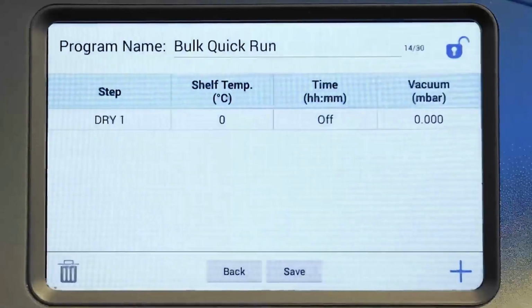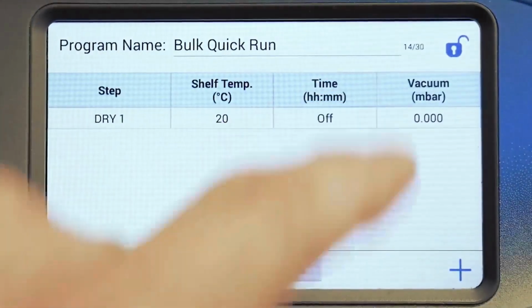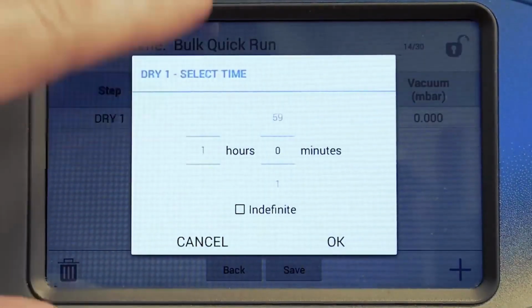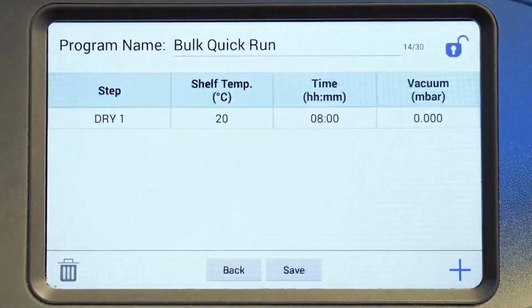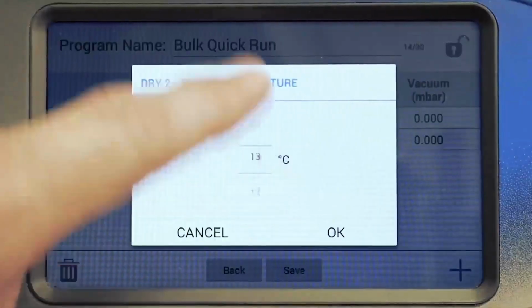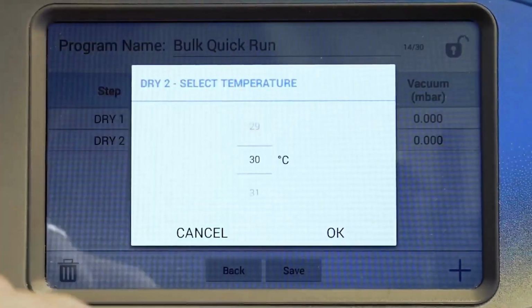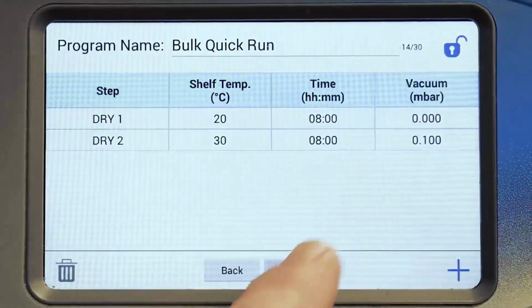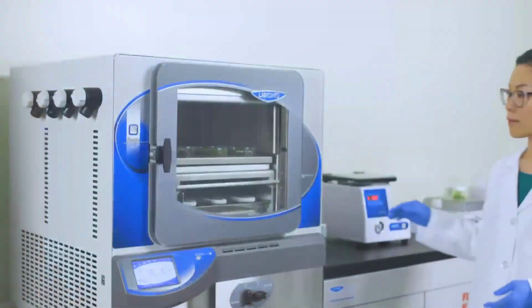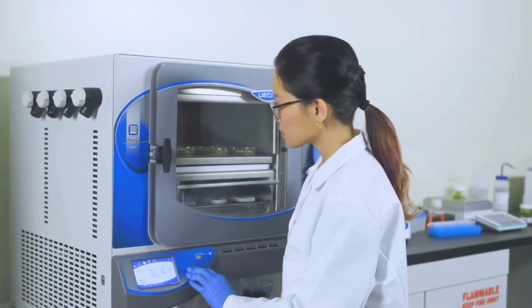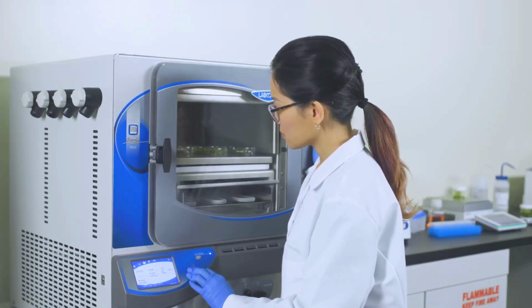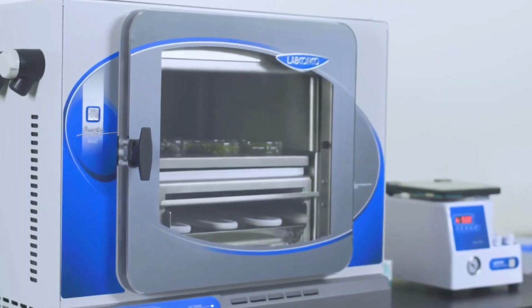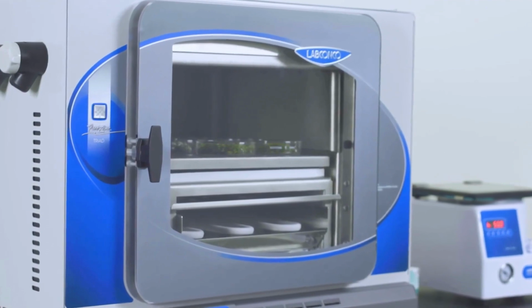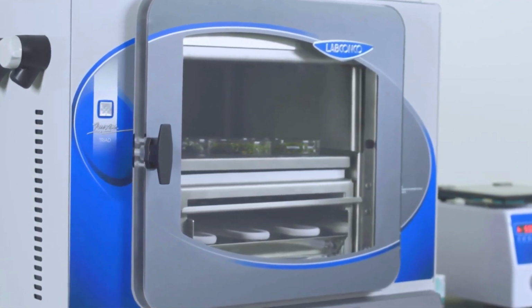Add a sequence of steps to your program. Each step can include parameters that are chosen from the drop-down menus for time and vacuum level. If you choose a plug-and-play accessory, like heated shelves or a tray dryer, shelf temperature can be programmed here as well. For models that include pre-freezing, the max cold option can be chosen. In this mode, the cooling rate of the shelves is not controlled and the shelves cool as quickly as possible.